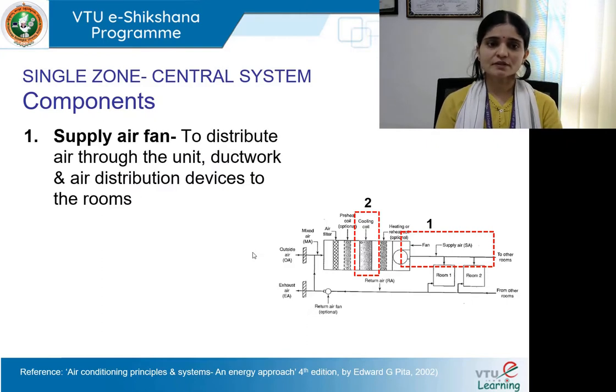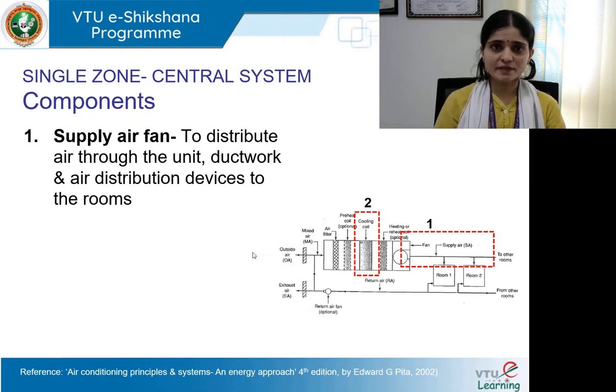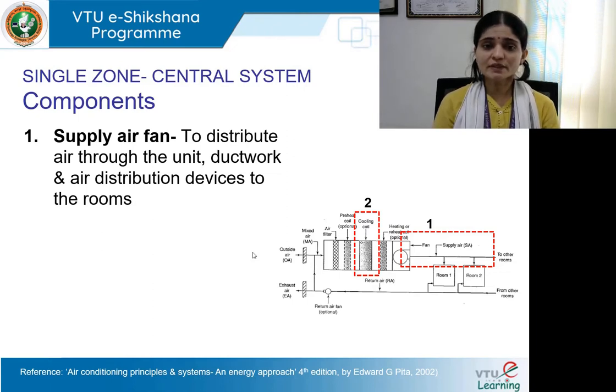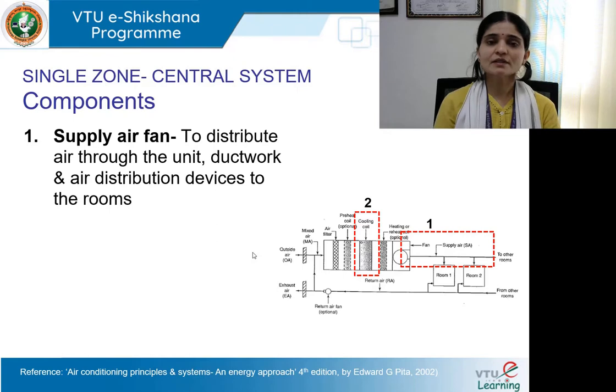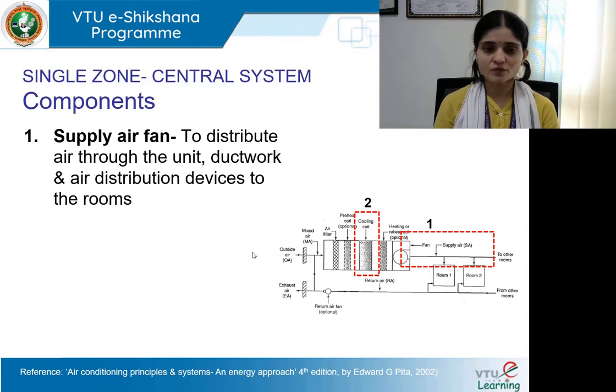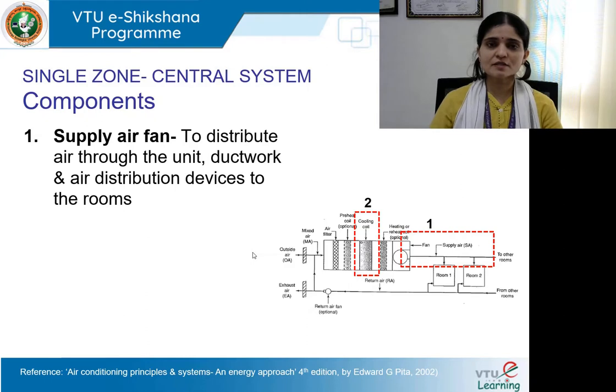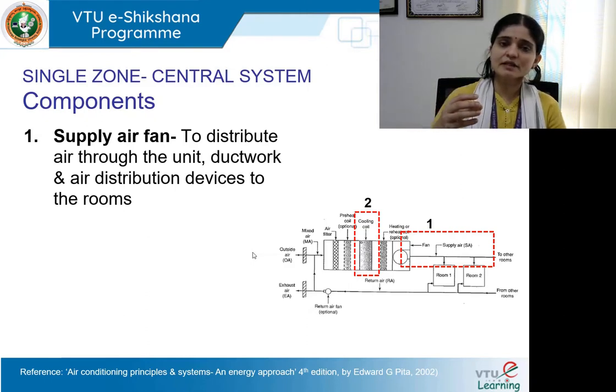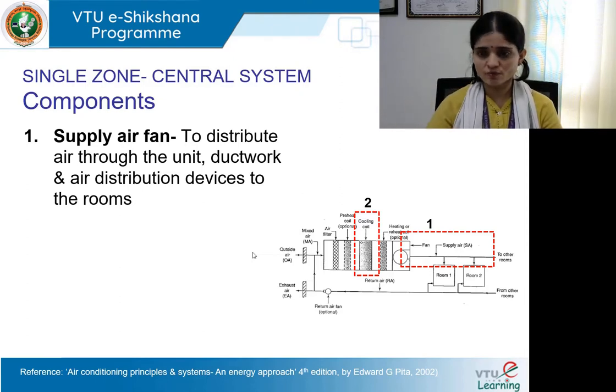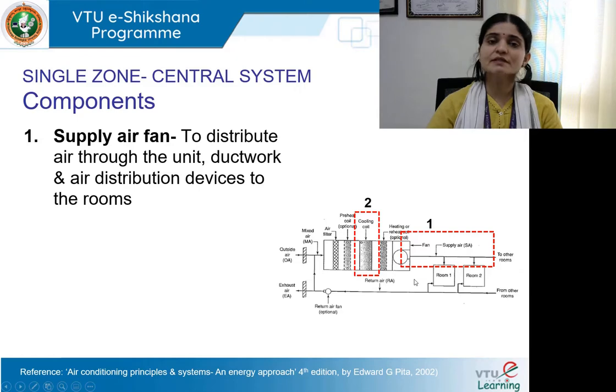We will understand the components step by step. Number one: the supply air fan, marked to the right side. It is used to distribute air through the unit, ductwork, and air distribution devices to the respective rooms. The supply air fan handles the final output — that is, the cooled, cleaned, and dehumidified air — and supplies it through the ductwork to the terminal end, which is the air device where cool air enters the room.